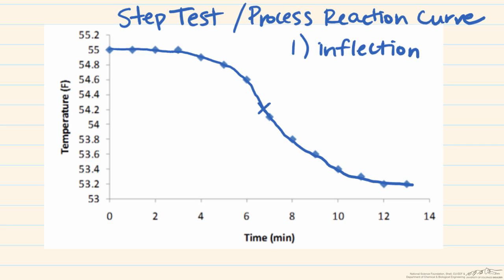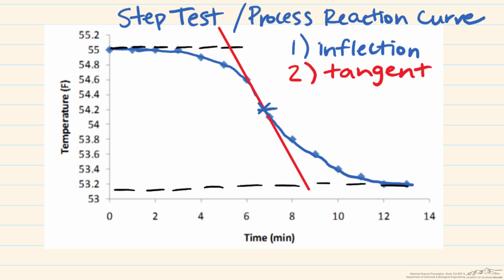And here we will just estimate the inflection point as somewhere around here. The next step is we have to develop a tangent line that runs through the inflection point. And then what we do is take a look at where the process crosses the initial value and the final value.